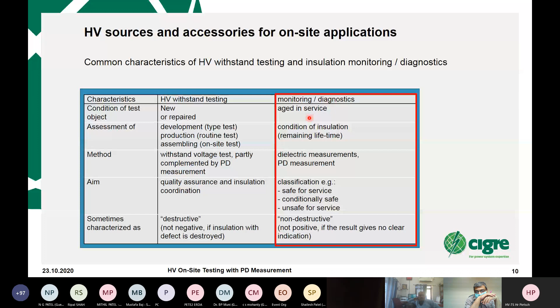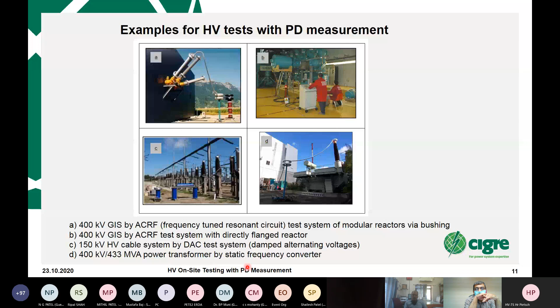Here now are different examples which were covered by this technical brochure. On this side, you see a GIS with bushings. There's a resonant test system outside, and so one phase is applied with voltage, 400 kV GIS. Another is a gas insulated GIS inside the substation with a so-called resonant test system, which I will shortly explain later. And the other one shown here is with damped AC voltage. How it works, I will also explain. And there's another example for testing a power transformer, again with a so-called static frequency converter.